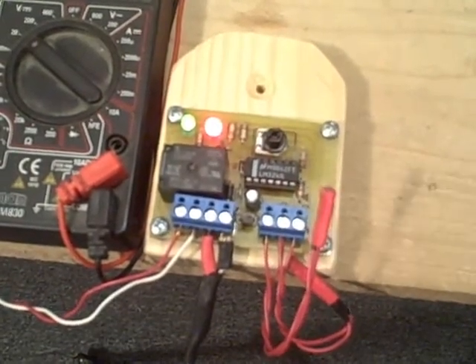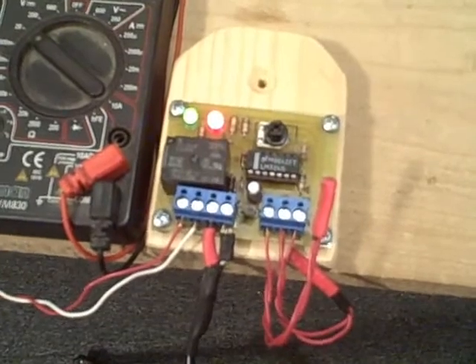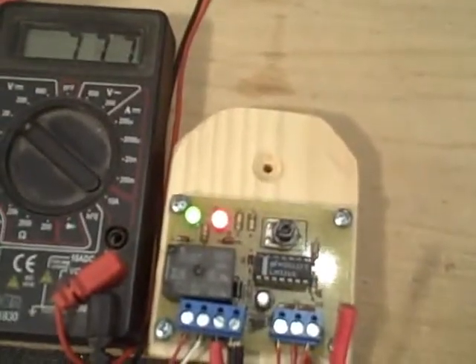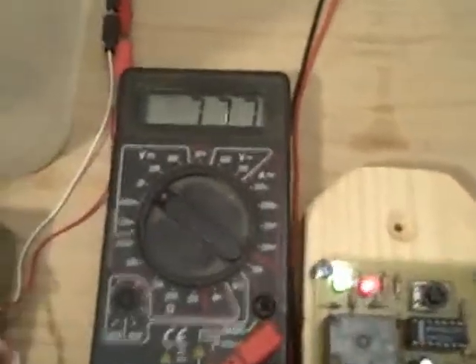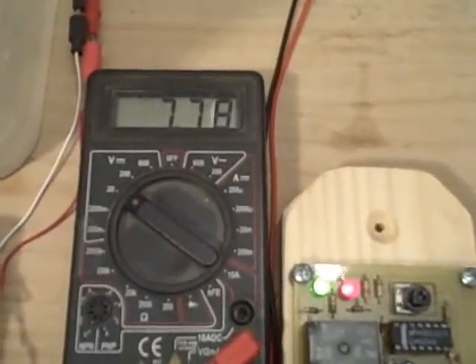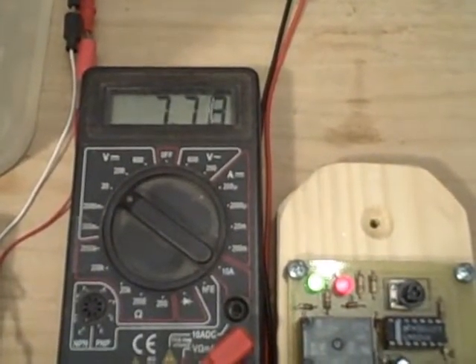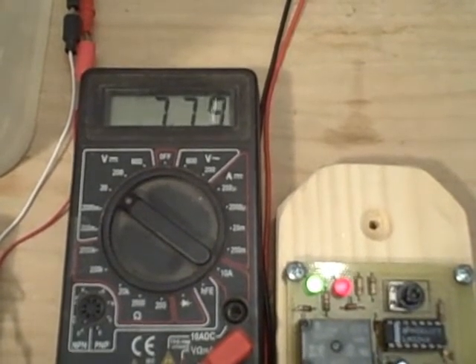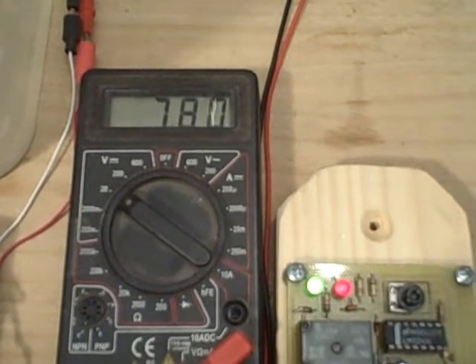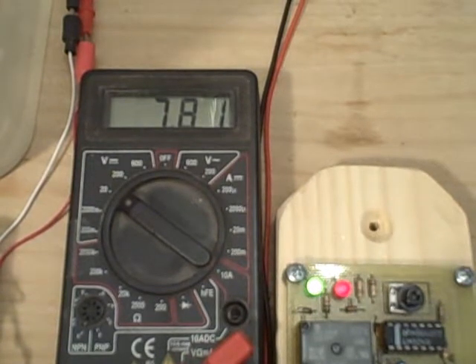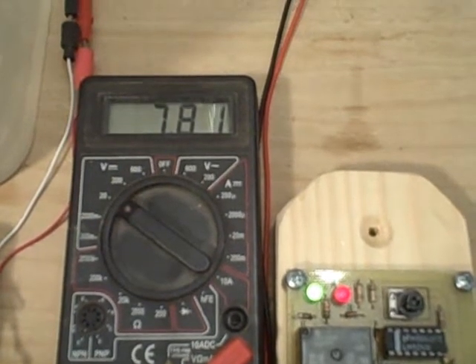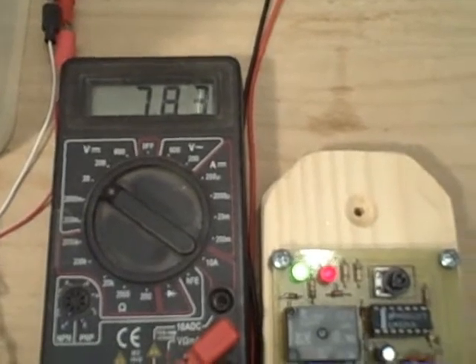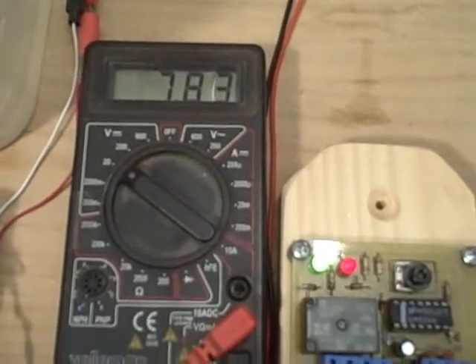We'll get it nice and hot so it'll stay on for a little while. The length of time that it stays on can be adjusted with the differential adjustment. You can see the output voltage is 7.78 volts, and that's enough to keep the pump flowing. Normally, you're going to want a voltage closer to 12 volts. But if it works at a minimum voltage, you know it'll work at a higher voltage.